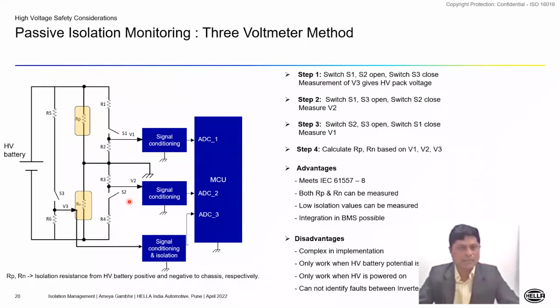So let's look at the popular method, the 3 voltmeter method, which is used for isolation monitoring. And why is this called passive isolation monitoring? As I just said, this method requires a constant DC voltage. If the DC voltage is fluctuating, then obviously there will be an error in the measurement, and either the system may not be able to measure the fault resistance RP or RN shown here, or it will require some software adaptations. So basically, let's understand how the passive isolation monitoring system works, which is, as of today, the most commonly used method.